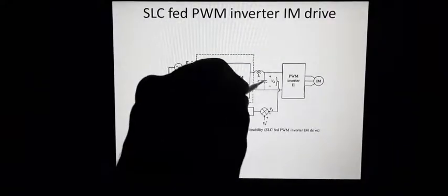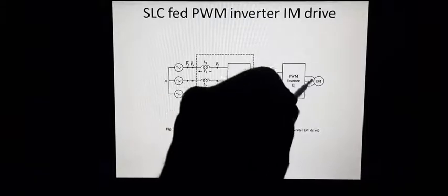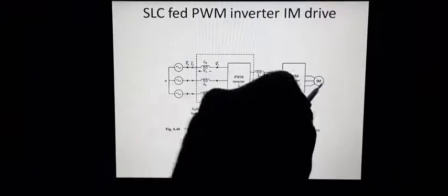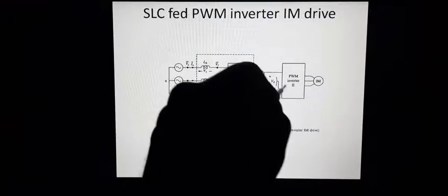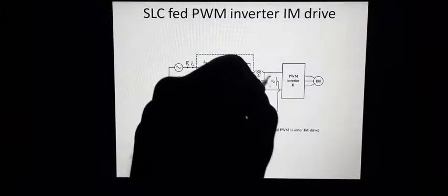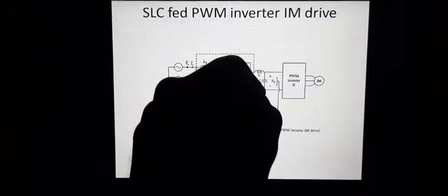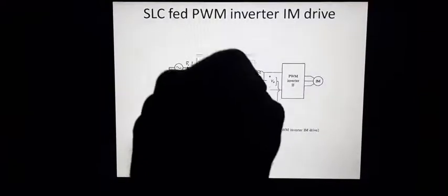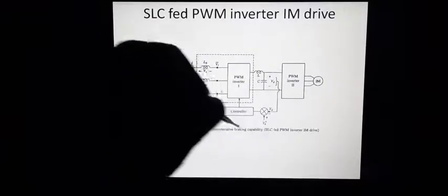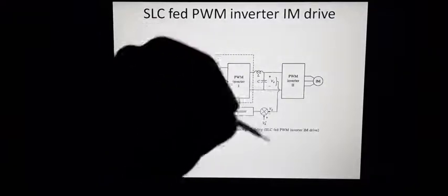See, just like what we have mentioned here, when the induction motor is overloaded, the overload power has been supplied from this capacitor side, which results in a voltage sag here. Comparing with the reference value, the voltage has taken a dip. So in order to overcome that, we have used this controller arrangement.